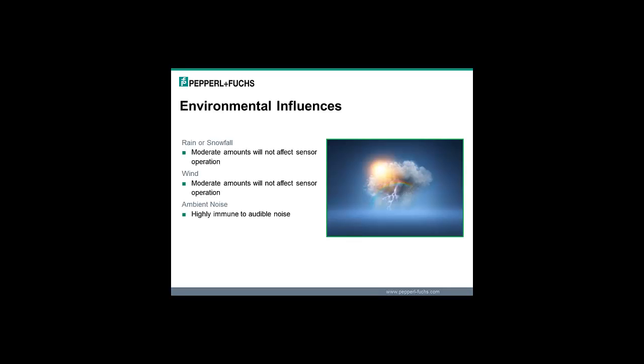Rain and snowfall in moderate amounts does not have any effect on an ultrasonic sensor's operation. Heavy rain, heavy snowfall, yes, that will affect an ultrasonic. Likewise, wind. Moderate amounts of wind have no effect on ultrasonic sensors' operation, but I would not put them in a hurricane. The echo is going to get blown away, and the sensor will never see it. So moderate amounts of wind, no problem for an ultrasonic sensor.